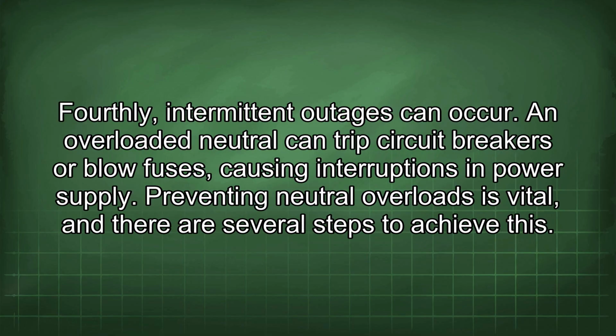Fourthly, intermittent outages can occur. An overloaded neutral can trip circuit breakers or blow fuses, causing interruptions in power supply. Preventing neutral overloads is vital, and there are several steps to achieve this.